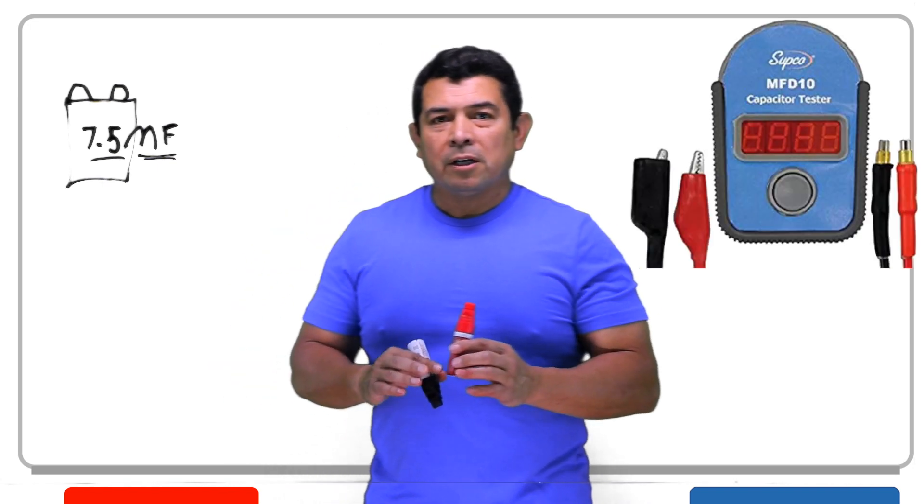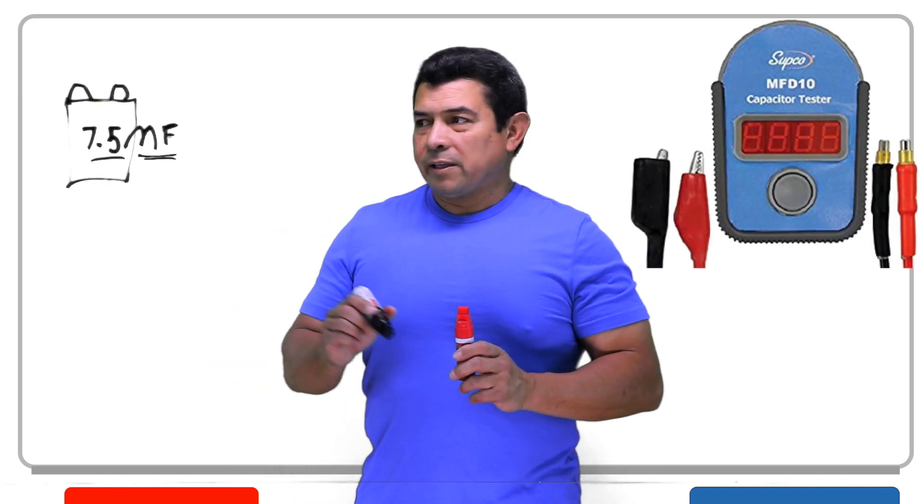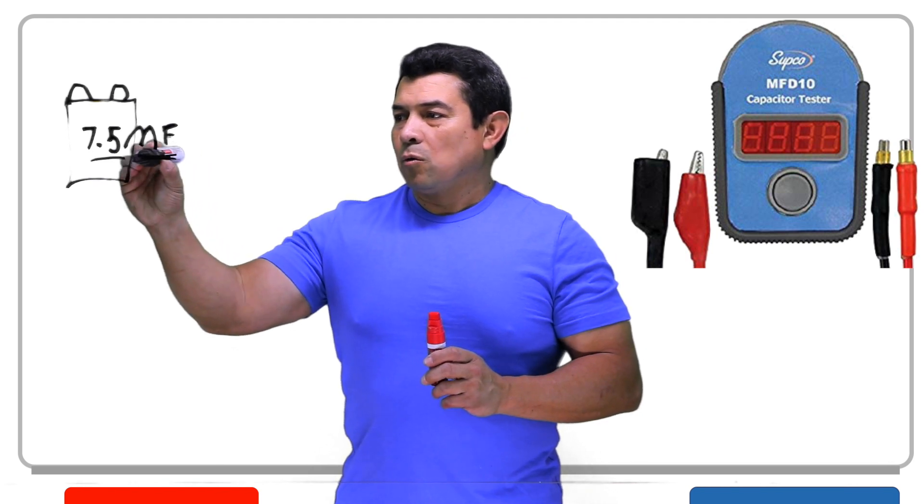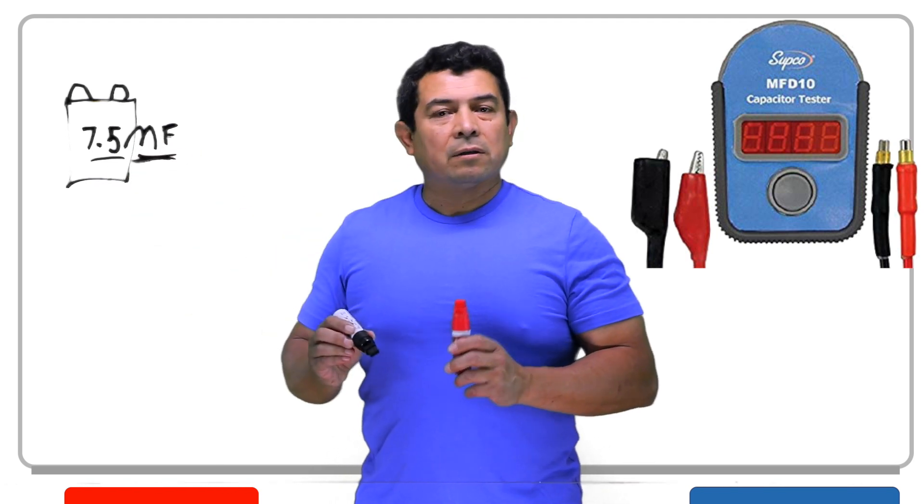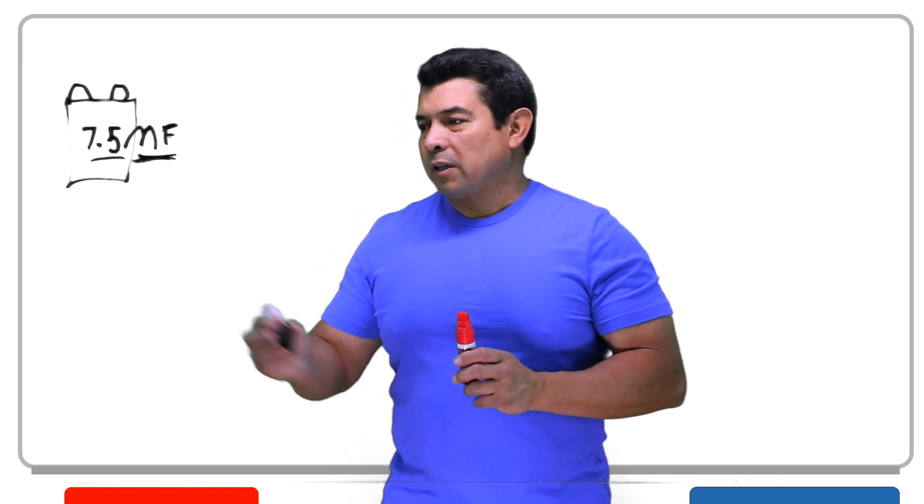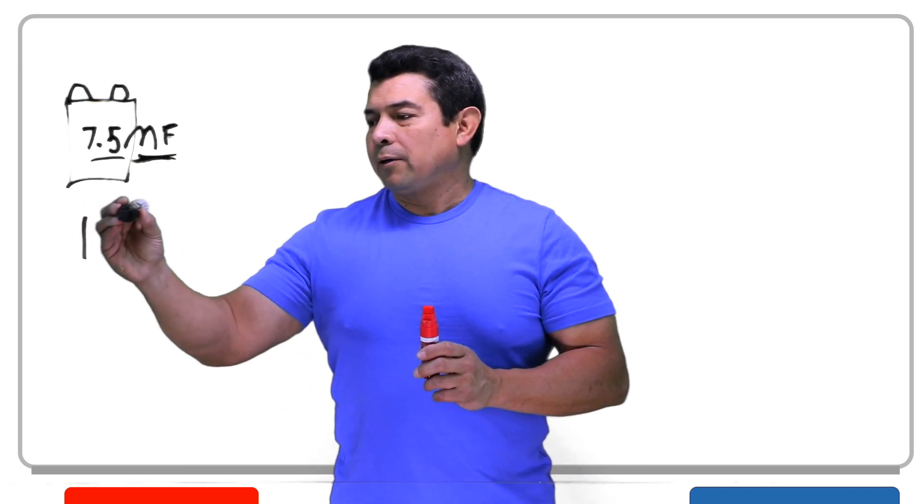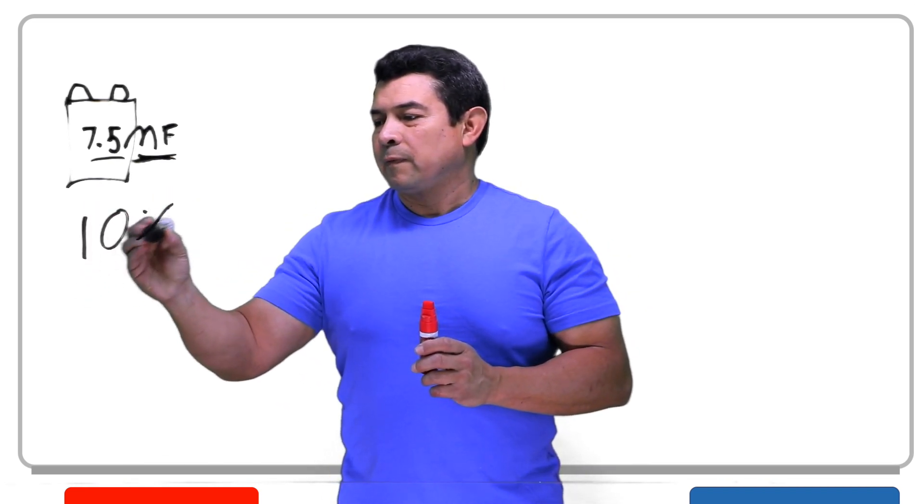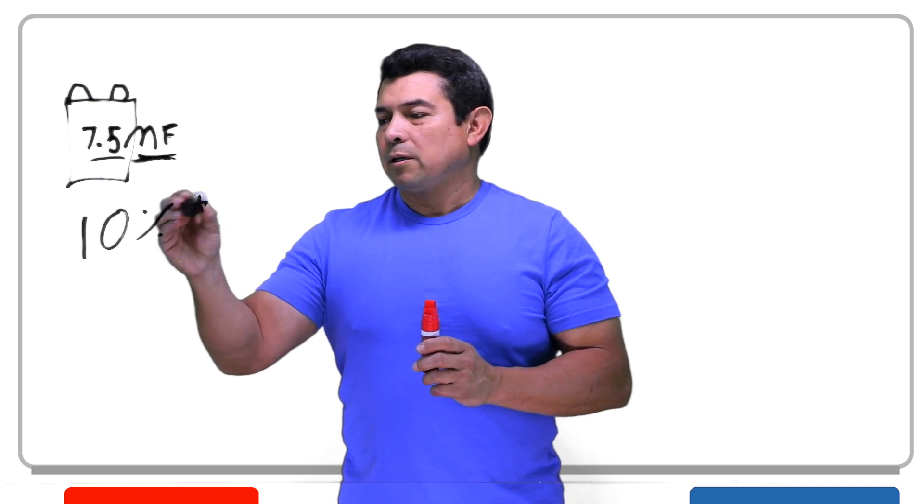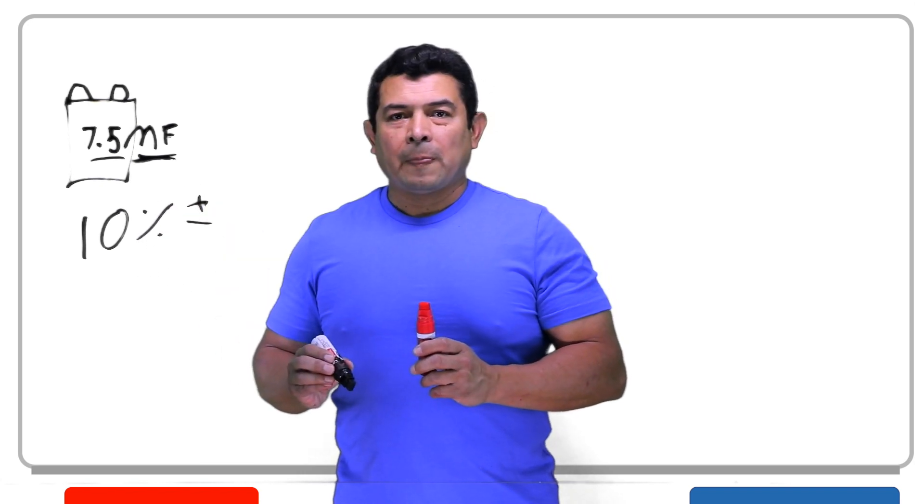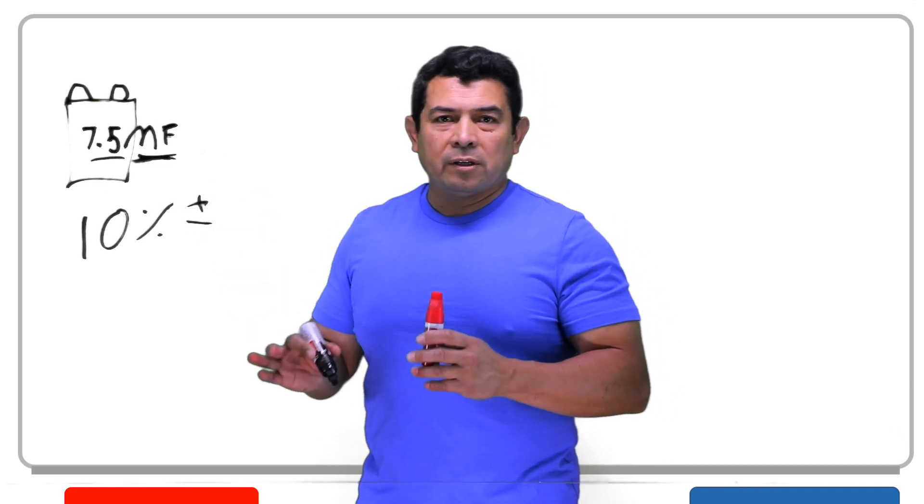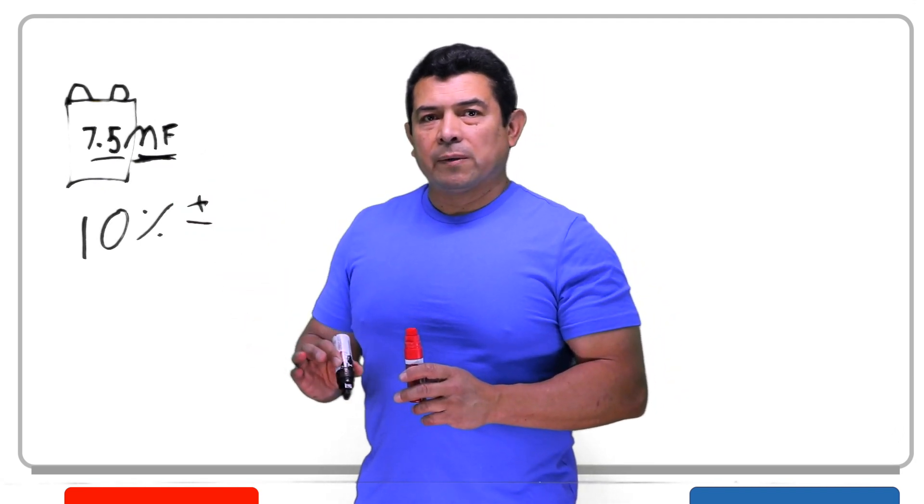But if you have a capacitor tester, the capacitor tester will actually tell you what the microfarads on that capacitor are. Now in most electrical equipment, we're allowed how much leeway? Plus or minus 10%. So if this capacitor is within 10%, then we should be okay.